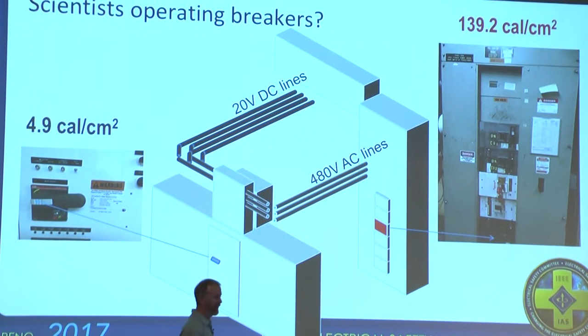This is a big magnet power supply for one of our cryogenic magnets, 1,000 amps, 480 volts on this breaker here. And this is their lockout-tagout point. We found out they were switching this without PPE at almost 140 calories per centimeter squared.